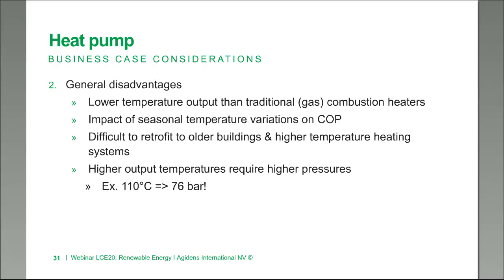Of course there are always ways to increase the temperatures — we mentioned the two-stage setup. There are also large industrial heat pump systems that can provide very high temperatures but which operate at extremely high pressures. There are examples of heat pumps which can provide temperatures up to 110 degrees but which operate at 76 bars. So that is not the most easy installation to build.